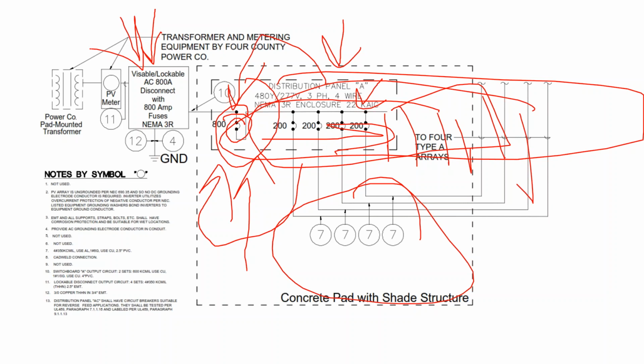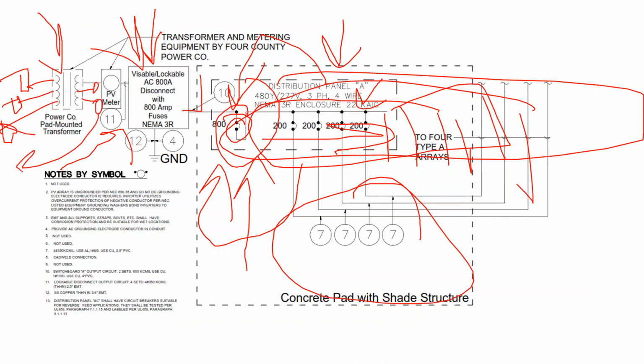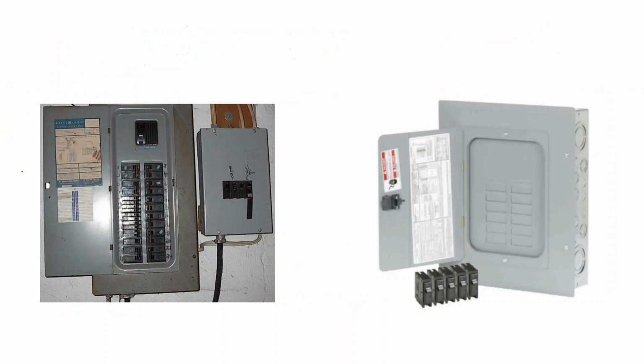And so to avoid the learning curve and going back to the utility and saying, can we get around your program? Because it was the solar incentive program that required the knife switch. We just divided it into 2 800 amp arrays with a knife switch disconnect, and it just wasn't a project issue. Your transformers get into this issue too, where you can be tapping on multiple services onto a transformer, and each of those services can have their own disconnect switch, provided that they're grouped in the same area. If there's more than that, then you have to combine those services together.